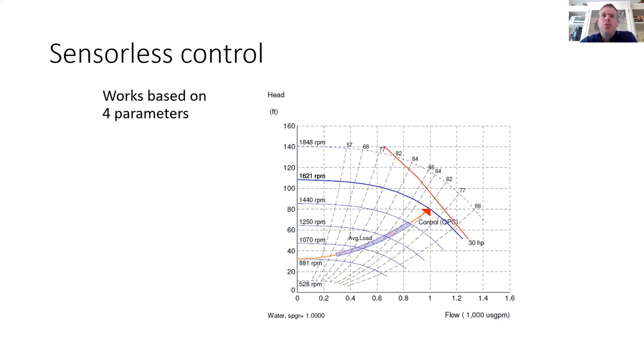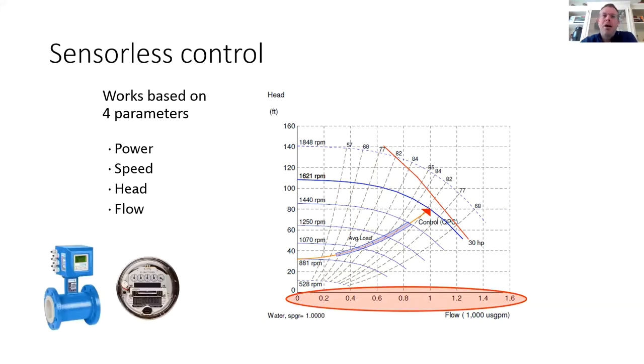So sensorless control works based on four parameters: power, speed, head, and flow. So our dynamic pump sizing and selection program works in the same way. If you input flow and head into our selection program, you get as an output power and speed along with impeller size, efficiency, pump size, etc. The sensorless controller reads power and speed from the VFD or the ECM to figure out the flow and head based on the tested pump map. Thus, the program always knows precisely where it's operating and could allow you to remove a flow meter and or a power meter.